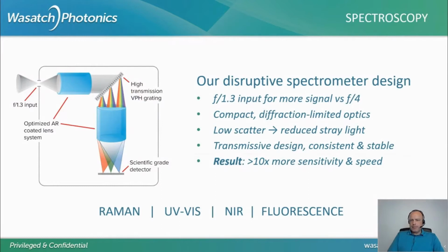What makes WASATCH Raman spectrometers unique? It's for sure the transmission grating that we are producing, but it's also our own optical design. This means we have an f/1.3 input compared to standard f/4. This brings more light into the whole spectrometer system and makes us much more sensitive compared to other spectrometers on the market. That's a great thing, specifically if you have low light applications like Raman or also fluorescence. Now it's time to show you a video of how easy it is to use our instrumentation.